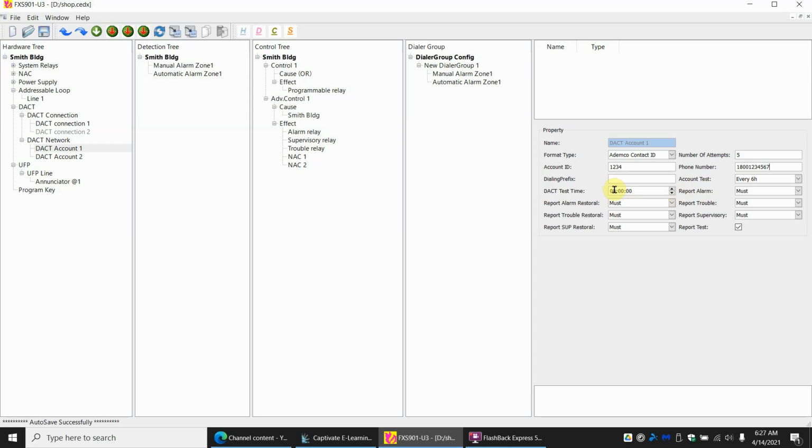So I like to make my DACT test time more daytime hours. 11 o'clock in the morning. They should be awake. For all these are musts, and we're just saying if anything happens, it must report out. And we are going to send out that test at 11 o'clock. That's right here. On DACT account 2, this is where you would put in almost all the same information.